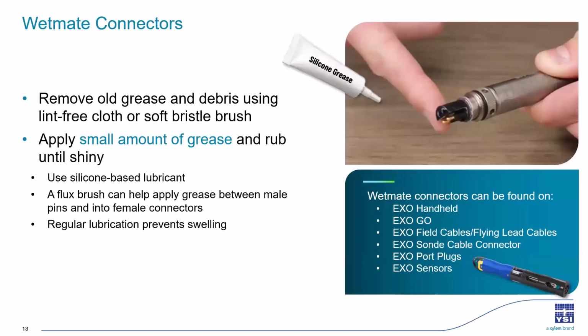Okay, now if you have wet mate connectors, like on your EXO, all the EXO sensors, cables, and accessories we have listed, I don't want you to forget about those. So we need to maintain the wet mate connectors regularly. Try not to leave your sensors installed for years at a time and never clean and lubricate them. If they're not regularly lubricated, it can cause friction, and it could cause the rubber to start to absorb water and swell. And that's when you might have issues getting your sensors back into your bulkhead.